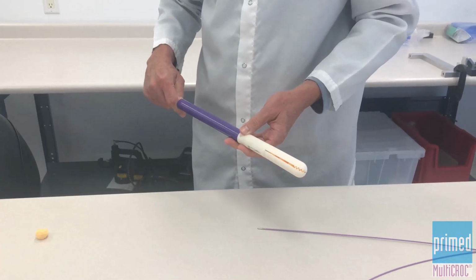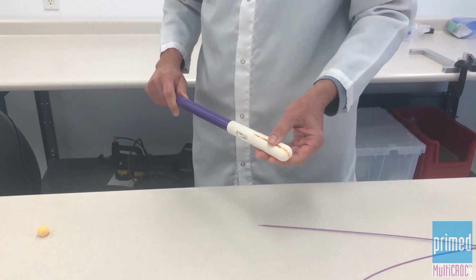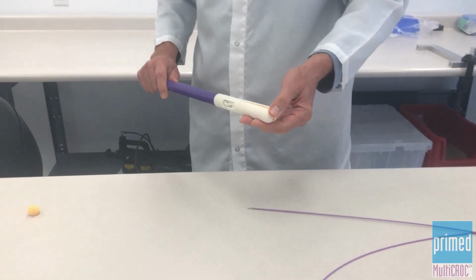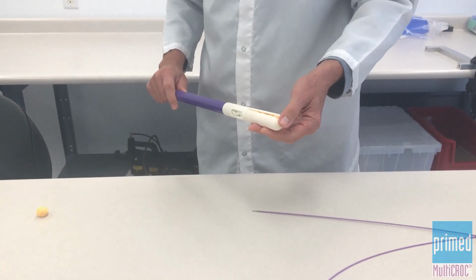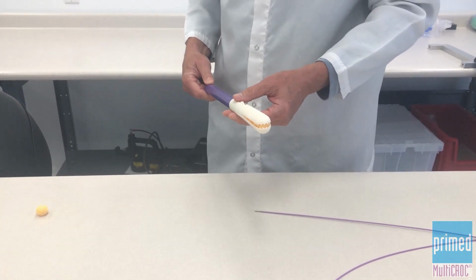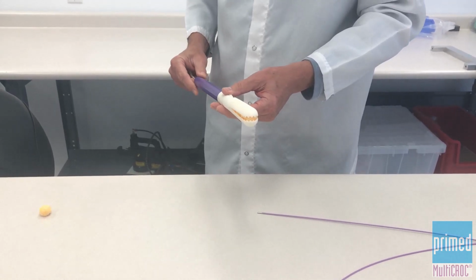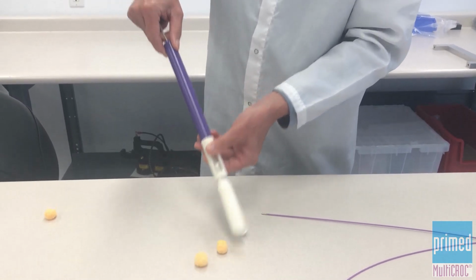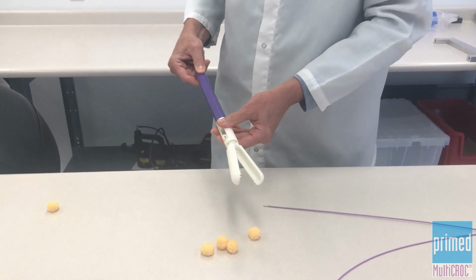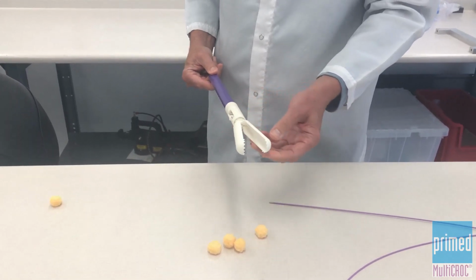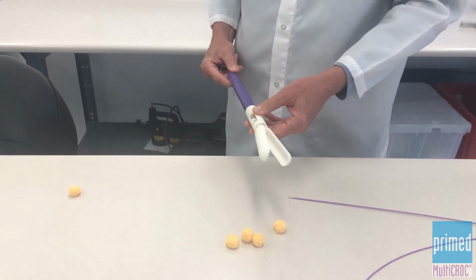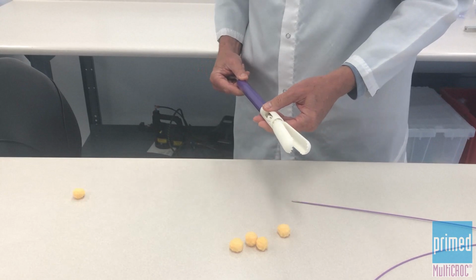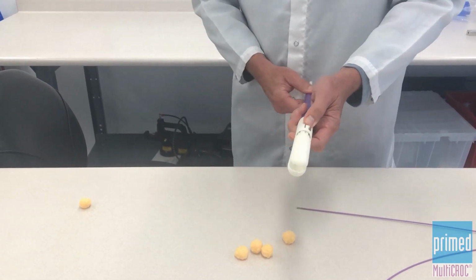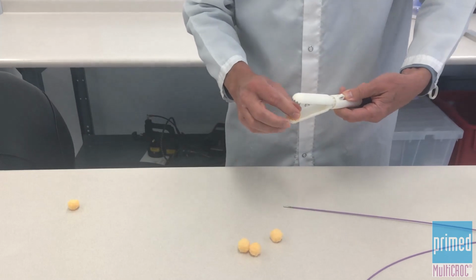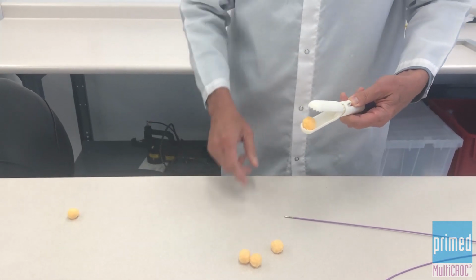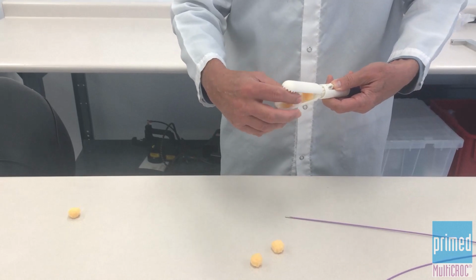The consecutively collected samples are stored in between the jaws. The tissue has some mucus on it, and it's sticky, and it stays between the elongated jaws. To remove the specimens from the jaws, simply open and shake in the jar with formalin, as the specimen will easily fall out, as there is no fenestration or any needle that will make the specimens stick into the jaws. Often there's a question whether the specimen can actually come out from in between the jaws during the procedure. And the answer to that is yes.